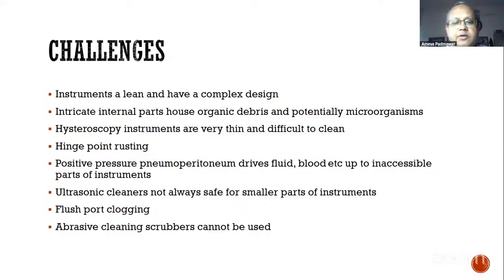and are very likely to harbor the blood and proteinaceous material, making a good substrate for microorganisms. Especially hysteroscopy instruments, the 5 French instruments, are very lean. So when you say 5 French, you have to divide it by a factor of 3 to know the actual diameter of these instruments in the metric system. So 5 French would be around 1.6 millimeter in its outer diameter. So 1.6 with a moving part is going to be very thin and lean. And obviously these instruments cannot be taken apart and they are difficult to clean.